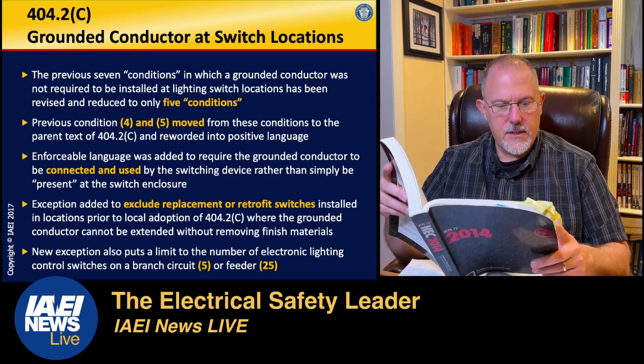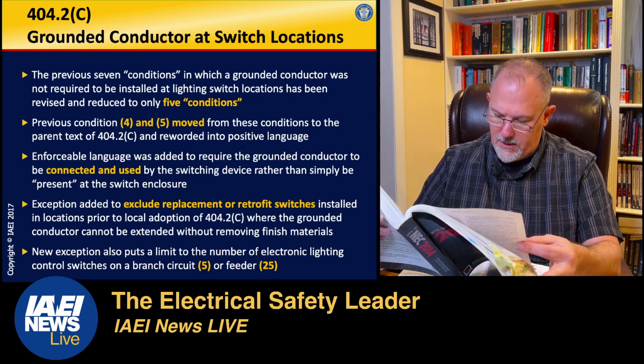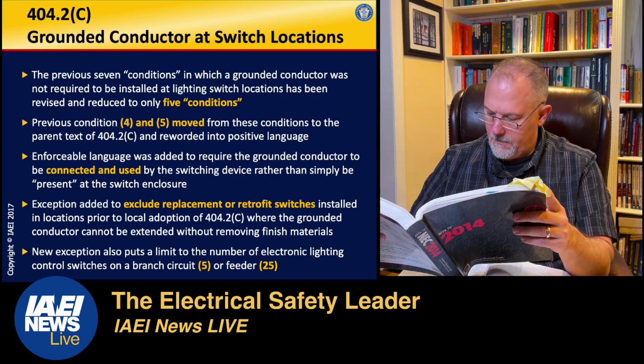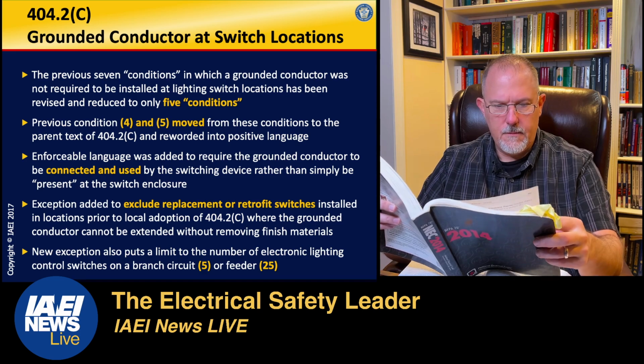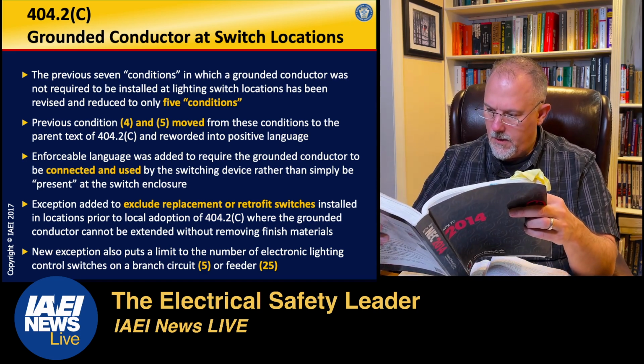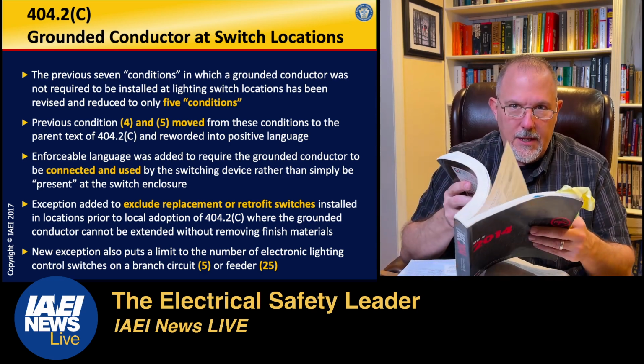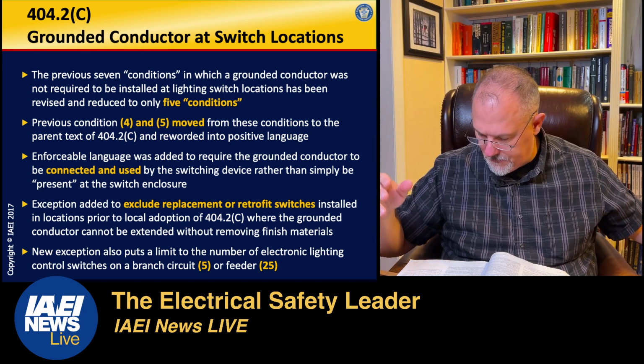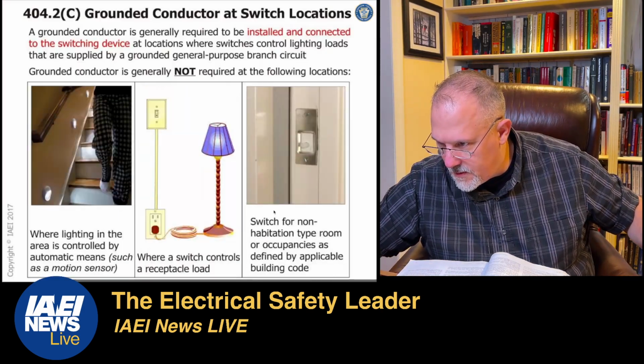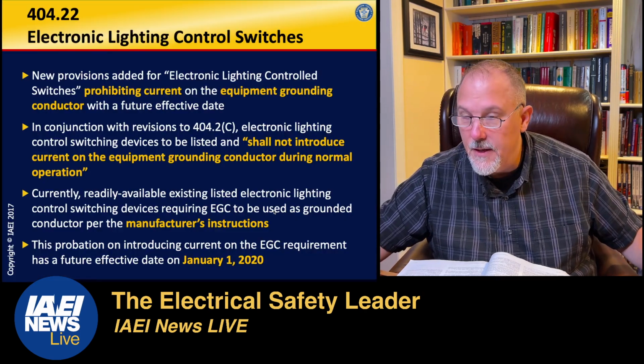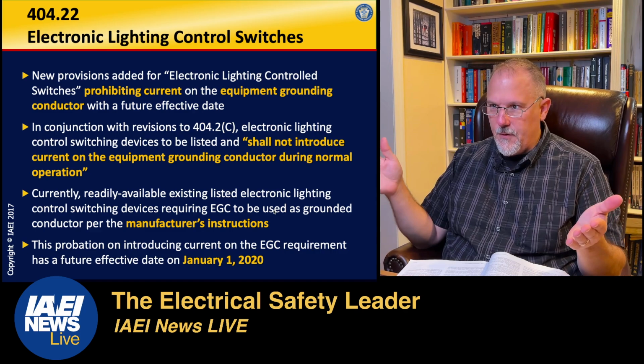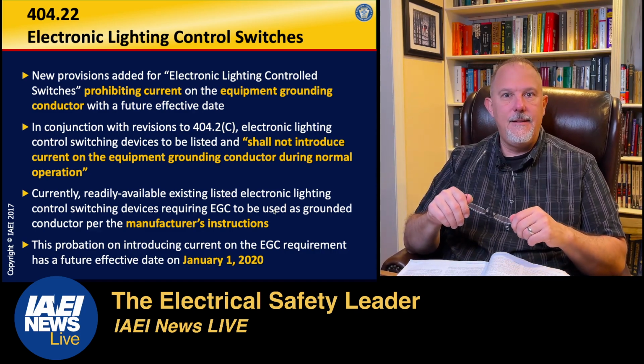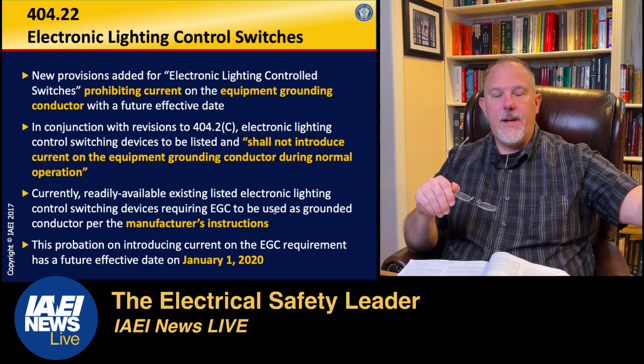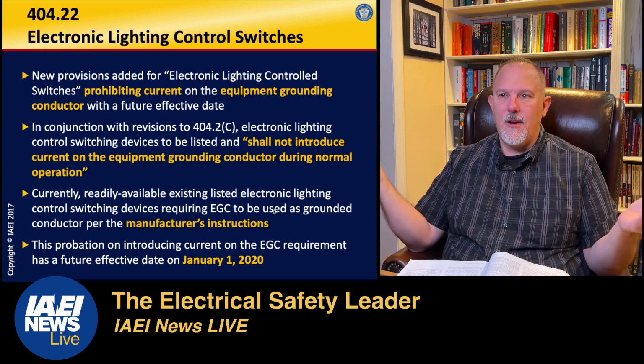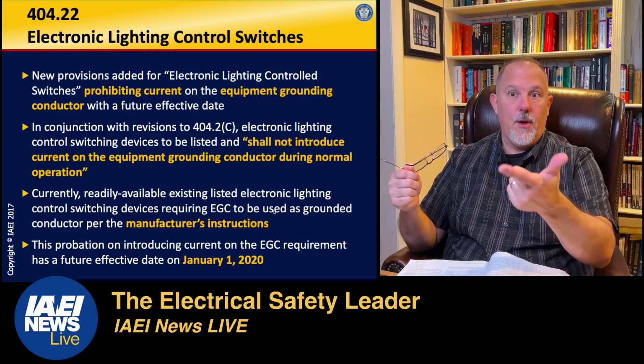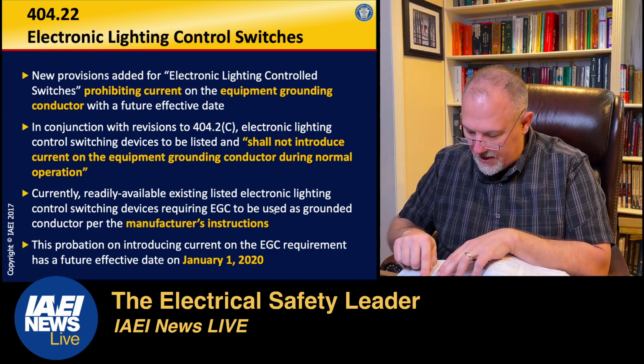And there's nothing else. I can honestly say there's nothing in here that I would say was moved over there. All right, so what do we see? We see in 404, in the 14 code, they introduced this. In the 17 code, they said, uh-oh, let me see, is there a 404.22? Yeah, look at that. 404.22, new, added for electronic lighting control switches. So they said, hey, we got this requirement over here, but now what about the requirements for these electronic lighting control switches? We want them to be listed. So now they're required to be listed.